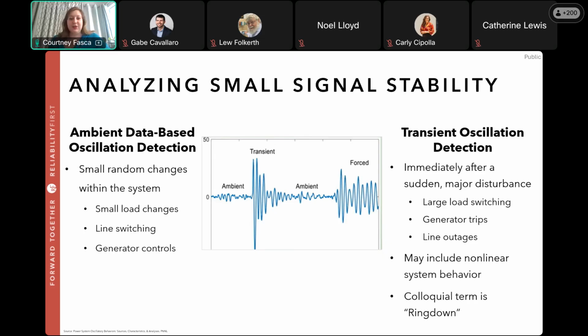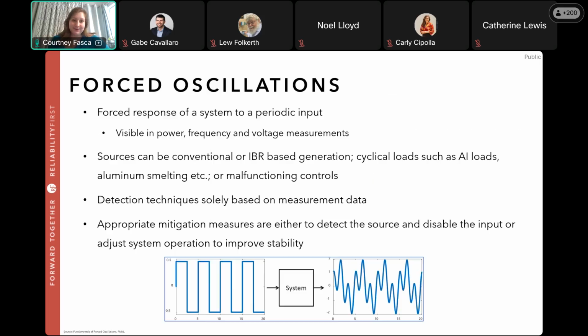So remember, this doesn't always mean the bike is going to crash or the system won't recover when you have this. So for the ring down oscillation detection, that basically involves analyzing the small signal stability after a major disturbance. The advantage here is that it has high accuracy in the frequency and damping estimation, and it has a faster computation time because you have shorter data windows to actually look at. It's also not reliant on system models being available and accurate. However, it does require an actual disturbance to be present, because it's not continuously monitoring, and it means that there's less data frequently available.